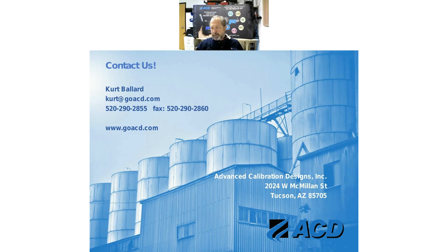So the upfront cost is pretty substantial. If you buy our most expensive instrumentation, you're looking at about $2,500 US to get set up, and then you have replaceable generating cells after that. So you keep the instruments. You see a lot of these Cal 2000s and GENies that have been out for years and years, 15 years, 10 years. So the instruments last forever. The consumable is the generating source. And those are sold with different amounts of hours that we equate so that you can see an apples to apples comparison. 1 hour of use we equate to one 58-liter cylinder. If you had a hydrogen sulfide cylinder that was 58 liters, and you have a 1 liter per minute regulator, it lasts for 58 minutes. So we say a cylinder is an hour.